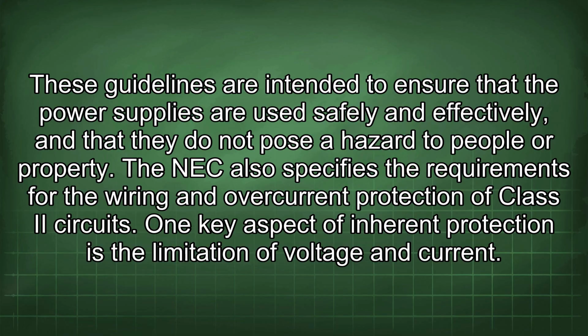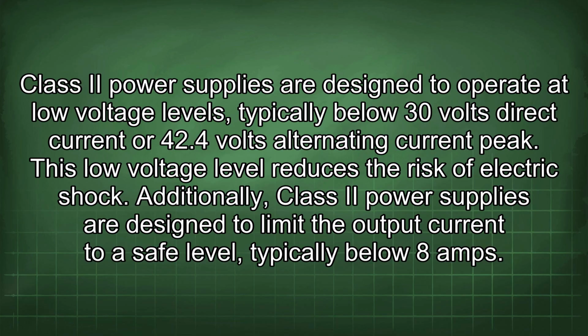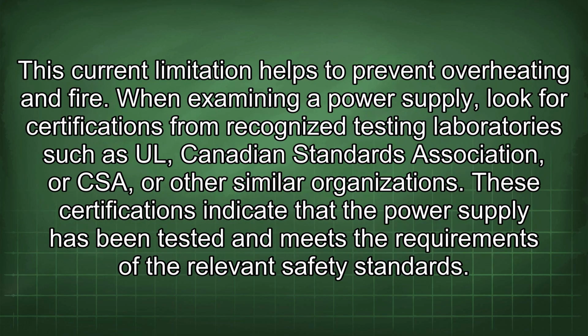One key aspect of inherent protection is the limitation of voltage and current. Class Roman II power supplies are designed to operate at low voltage levels, typically below 30 volts direct current or 42.4 volts alternating current peak. This low voltage level reduces the risk of electric shock. Additionally, Class Roman II power supplies are designed to limit the output current to a safe level, typically below 8 amps. This current limitation helps to prevent overheating and fire.